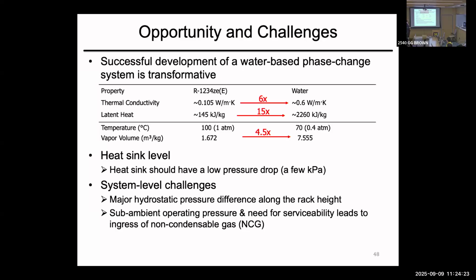There are also system-level challenges. If you have an entire system working at 40 kPa with a 2-meter rack, you get a 20 kPa difference between top and bottom, so the saturation pressure is different. How do you address that in sub-ambient operation? You also need serviceability—if one server isn't working, you pull it out and put in a new one, air gets in, the condenser stops working, and the saturation pressure changes. This is a real challenge.